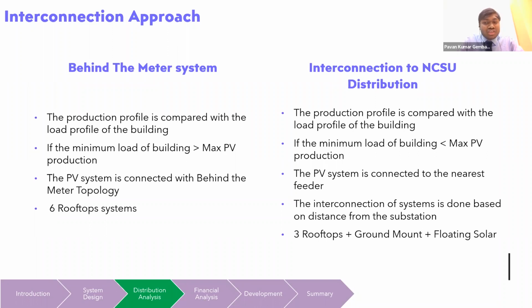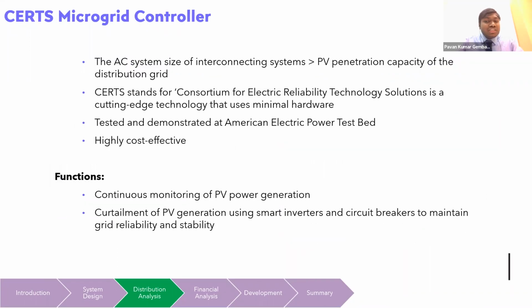The second configuration is to interconnect the PV systems with the nearest feeder. This configuration is used when the minimum load of the system is lower than the maximum PV generation of the system. So out of all the other systems, the 5 systems are interconnected based on the priority from the distance from the substation. The combined system size of these 5 systems is approximately 5.5 megawatts AC, which is higher than the PV penetration capacity of the distribution grid, which was 4.3 megawatts AC.